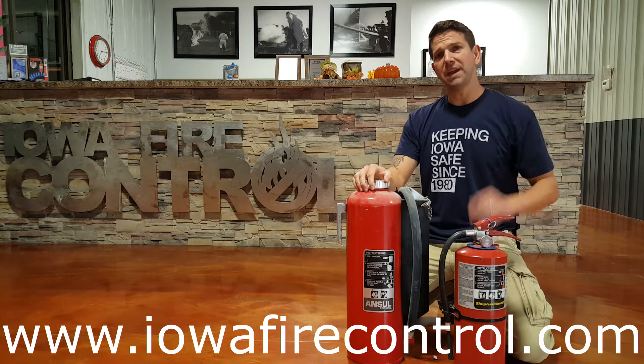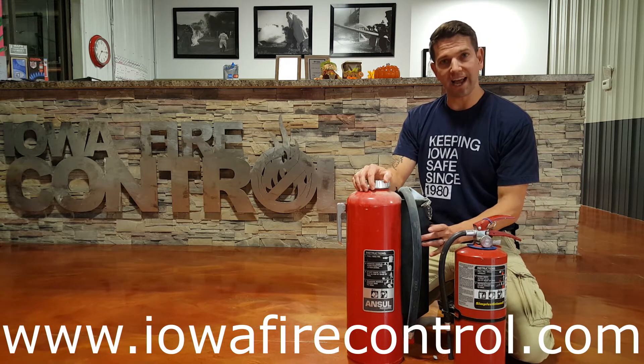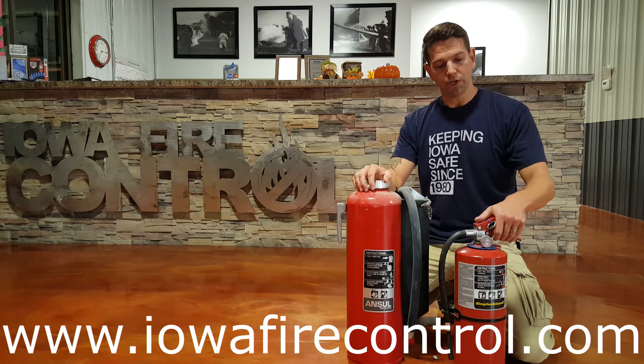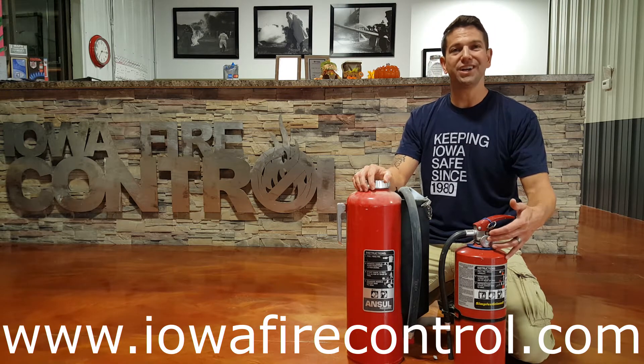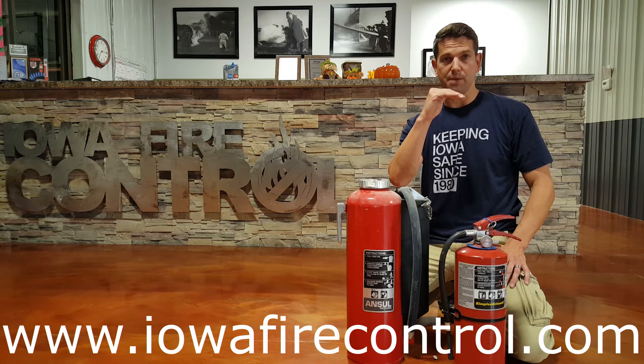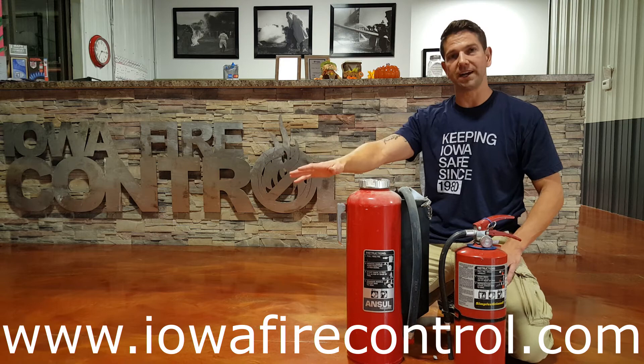The main reasons I would choose a cartridge operated fire extinguisher: one, it's at 220 PSI through a cartridge inside all the way through. With a stored pressure type fire extinguisher, when you squeeze the handle, you may start at 190 PSI, or if it's a high flow type stored pressure, you might start at 220 or 240, but as you pull that handle down, you drop pressure all the way down. You don't lose pressure with the cartridge operated, so the flow rate is consistent all the way through when you're fighting the fire.